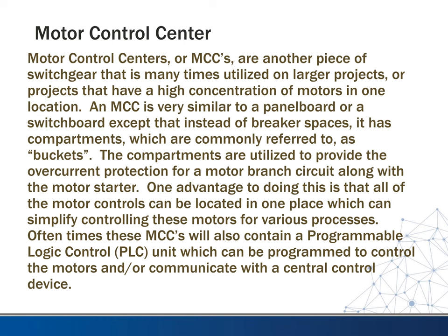Next, we want to take a minute to talk quickly about motor control centers, or you might hear them referred to as MCCs. These are another piece of switchgear that are at times utilized on larger projects or projects that have a high concentration of motors in one location. An MCC is very similar to a panel board or a switchboard, except that instead of breaker spaces, it has compartments which are commonly referred to as buckets. So you might hear someone talking about a bucket in an MCC. So this is just a compartment.